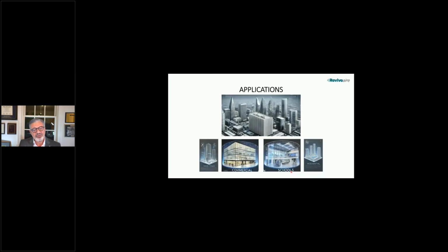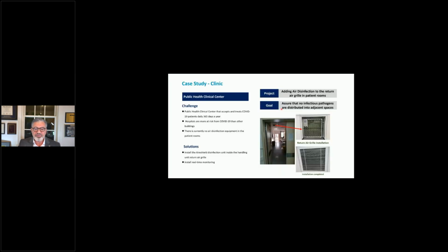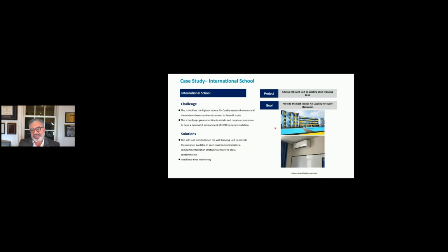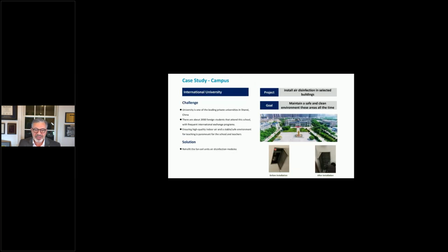Applications of these technologies include, in this case, a COVID ward where you can install the technology in the return air grill to protect the air going back into the central return air system and not have pathogen air mixing with other spaces. You can install these kinds of systems in split type units as well, whether it's UV lights, ionization, or non-thermal plasma, and they can be installed in fan coil units just as easily.